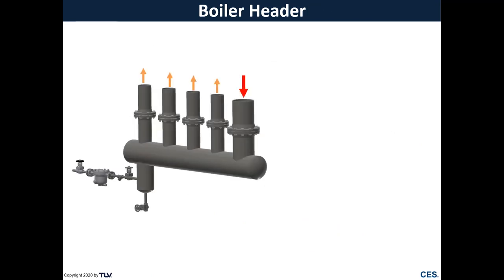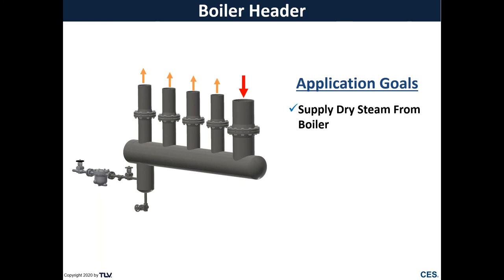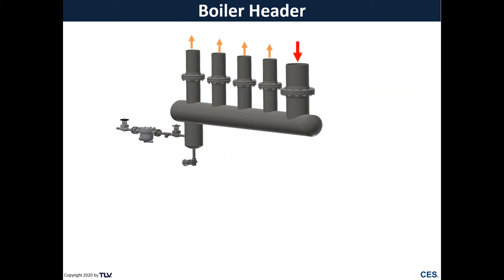Now getting into some other types of distribution applications. The first being our boiler header. This is typically the first condensate discharge location downstream of our boiler. The goal here is to supply dry steam from our boiler, and we could potentially see high loads due to boiler carryover. So this is going to be a much larger trap than our typical steam main drip trap.